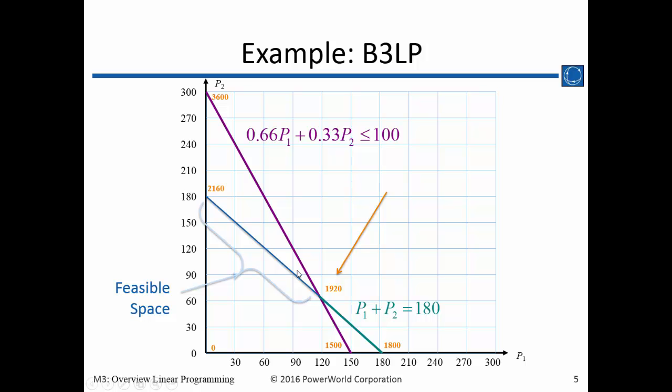So for controls in the actual system, any control that's at a limit is not a marginal control because it cannot provide a marginal megawatt. If a unit is at 0 or it's at its max, then it's really not part of this formulation. So generator bus 3 is not part of the formulation at the current operating point, but it could become part of the formulation if we have unenforceable constraints.